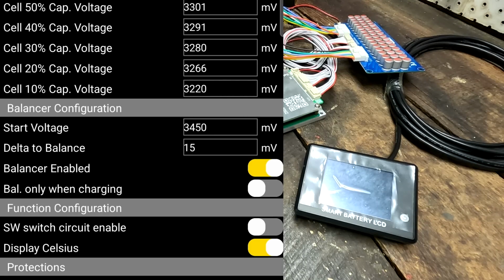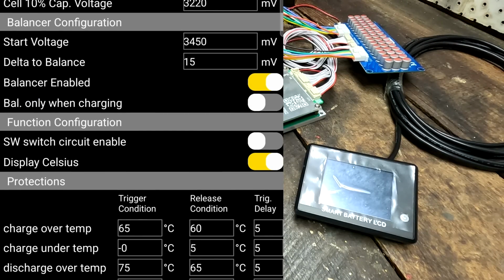Down here we've got the balancer configuration: start voltage at 3.45, delta to balance 15 millivolts. The balancer is turned on but not active, of course, and balance-only-when-charging is turned off by default, very nice to see - never turn on charge balancer, it's disgusting. The software switch circuit enable is turned off; this basically enables the function we see here on the BMS for the discharge switch.